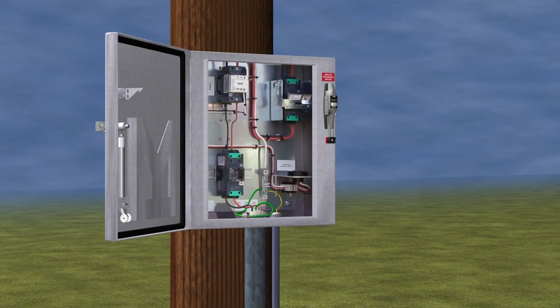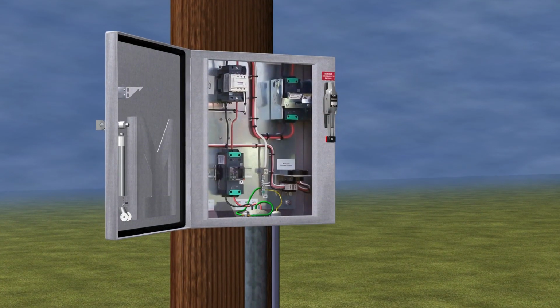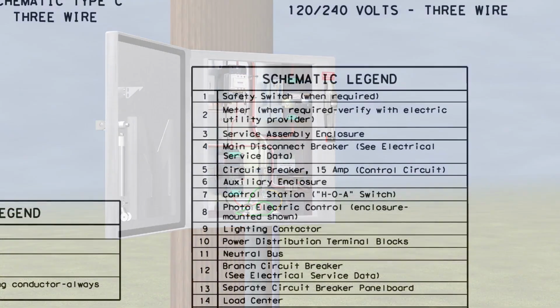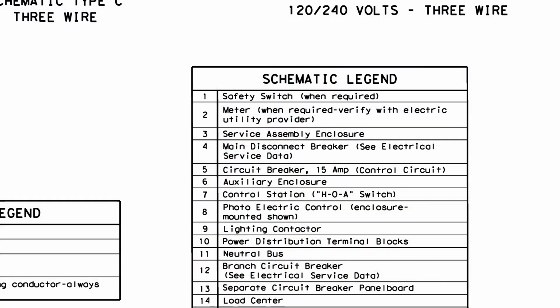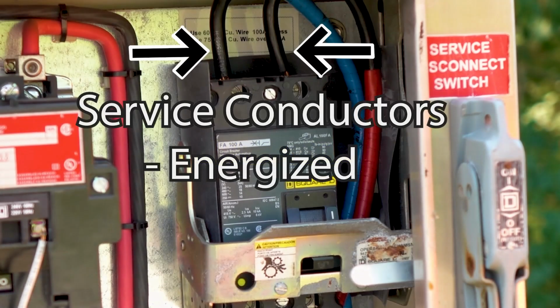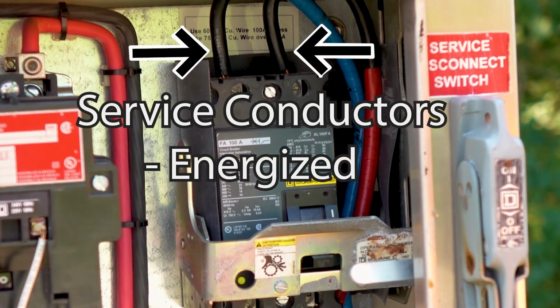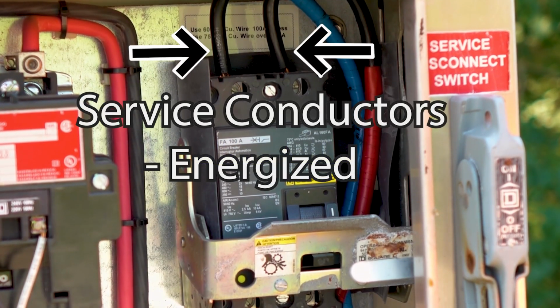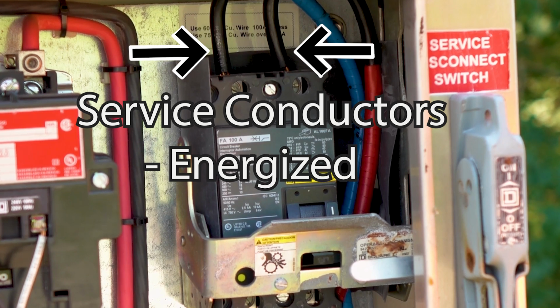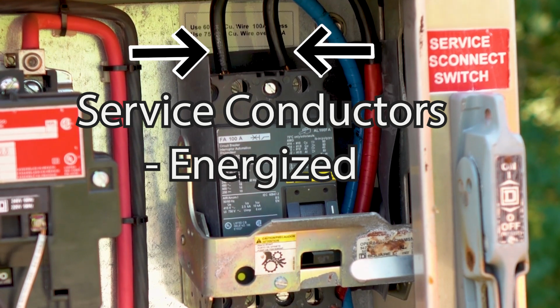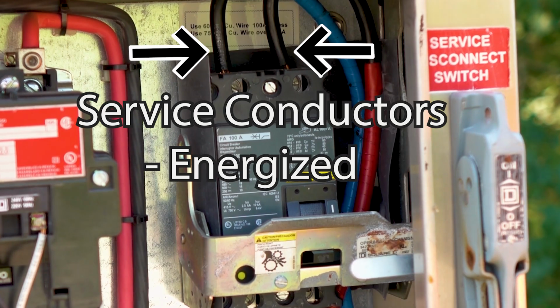Some parts of an electrical service remain energized even when the main breaker is in the off position. By looking at the schematic on ED6, we can find the main disconnect. This is number 4 on the legend. Two service conductors connect to the top of the main disconnect, also called the main breaker. These two conductors will still be energized even when the main breaker is turned off.